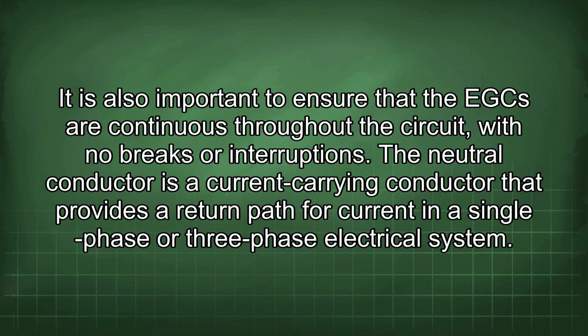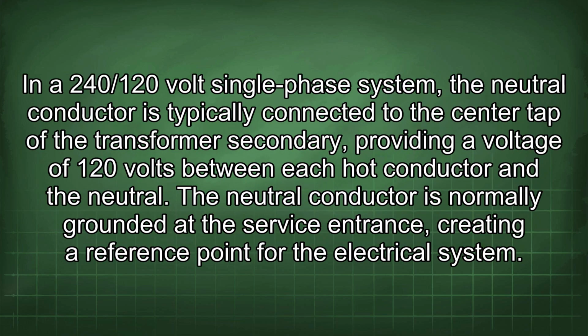It is also important to ensure that the EGCs are continuous throughout the circuit with no breaks or interruptions. The neutral conductor is a current-carrying conductor that provides a return path for current in a single-phase or three-phase electrical system. In a 240/120 volt single-phase system, the neutral conductor is typically connected to the center tap of the transformer secondary, providing a voltage of 120 volts between each hot conductor and the neutral. The neutral conductor is normally grounded at the service entrance, creating a reference point for the electrical system.